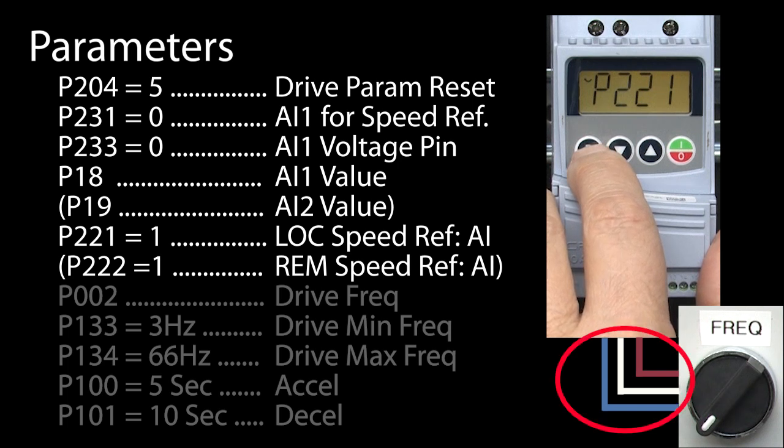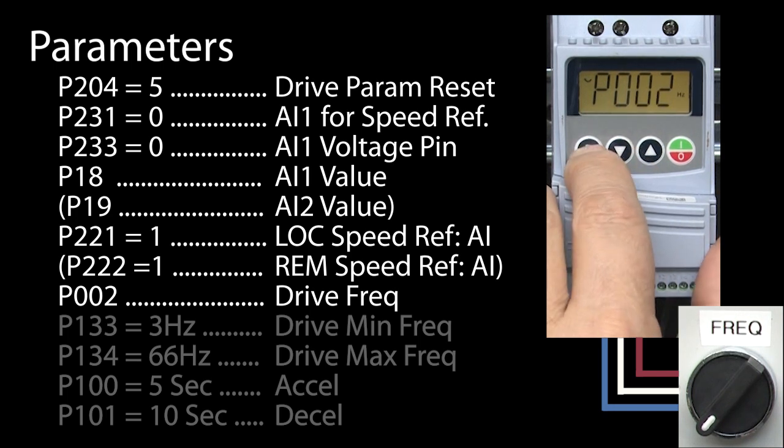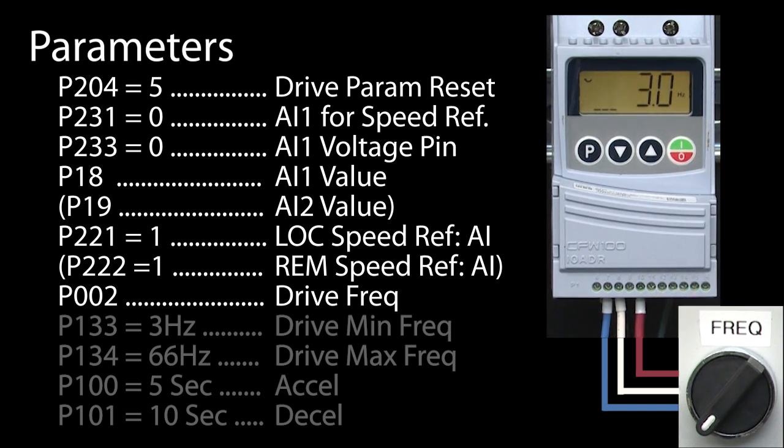So all we did was wire the potentiometer to the analog voltage input and change one parameter. I am going to scroll back to parameter 2 so we can see the drive's frequency and double-check that the potentiometer is all the way counterclockwise, which we know is zero. I will hit run, and the drive goes to its min speed, which we can change in parameter 133.